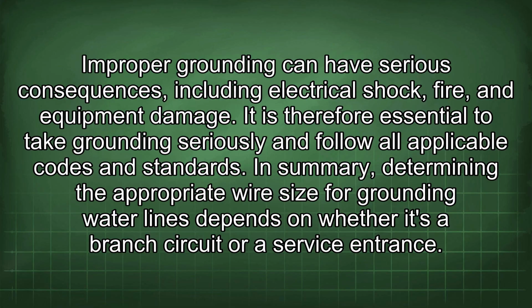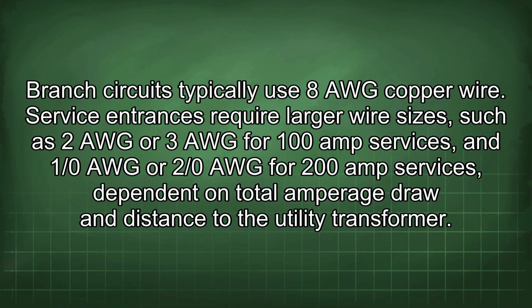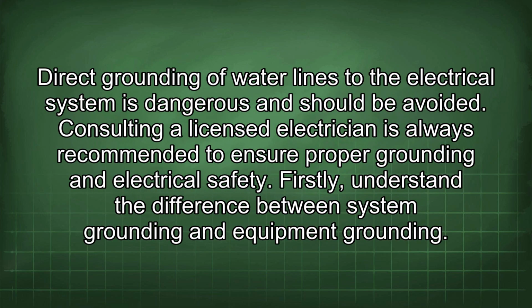In summary, determining the appropriate wire size for grounding water lines depends on whether it's a branch circuit or a service entrance. Branch circuits typically use 8 AWG copper wire. Service entrances require larger wire sizes, such as 2 AWG or 3 AWG for 100 amp services, and 1/0 AWG or 2/0 AWG for 200 amp services, dependent on total amperage draw and distance to the utility transformer. Direct grounding of water lines to the electrical system is dangerous and should be avoided. Consulting a licensed electrician is always recommended to ensure proper grounding and electrical safety.